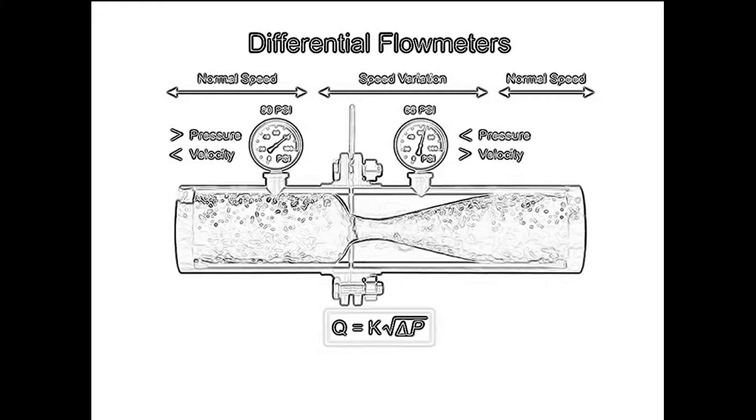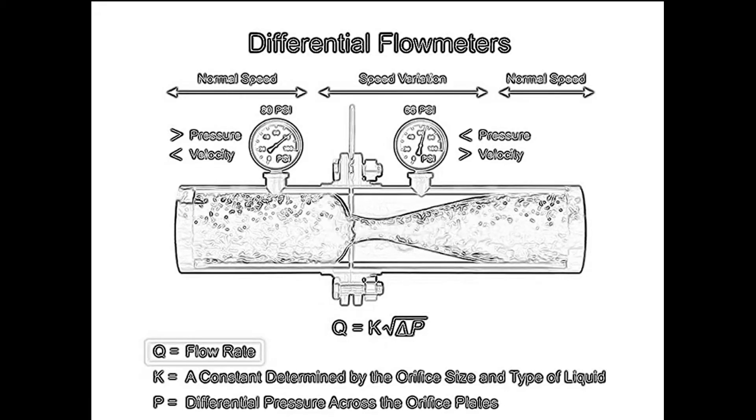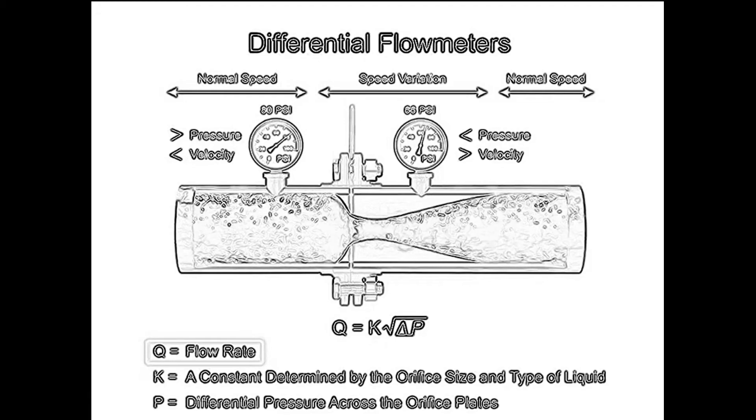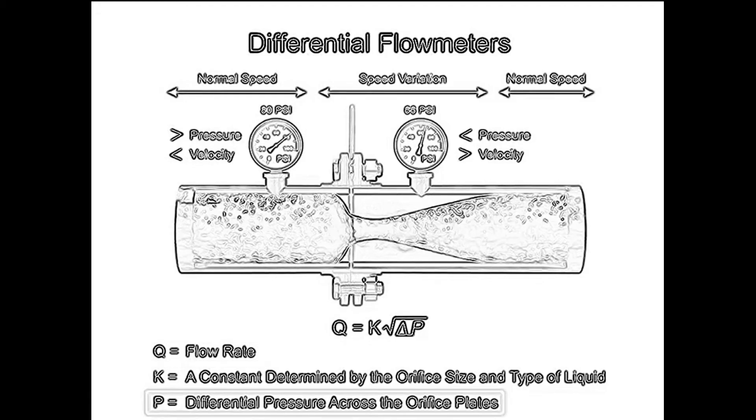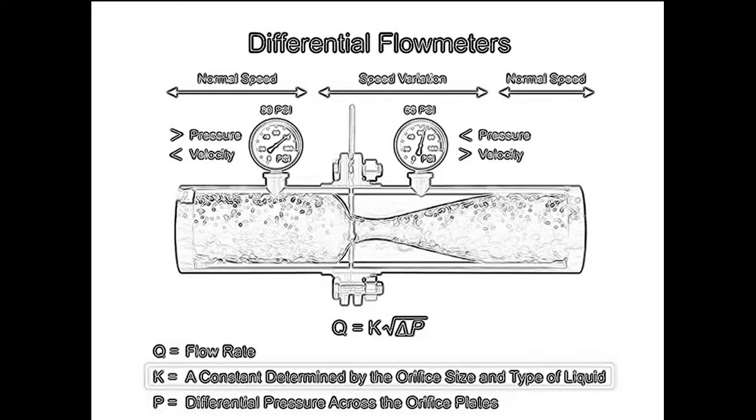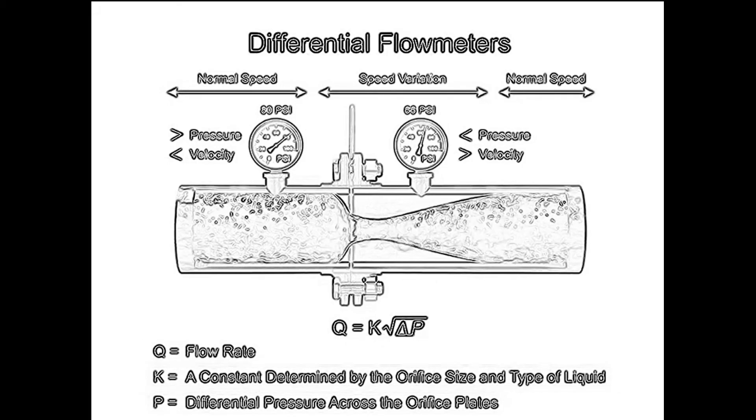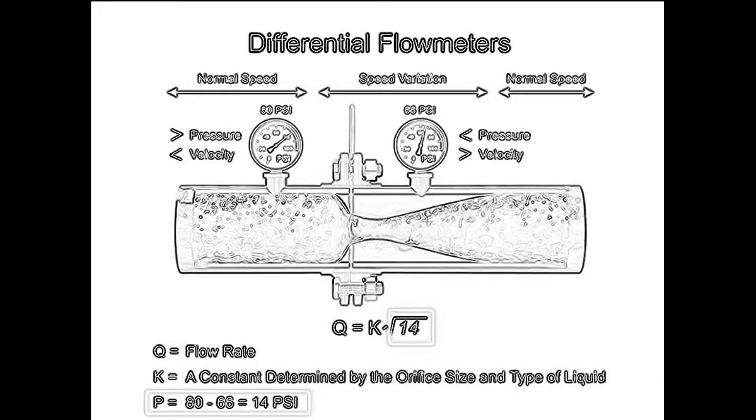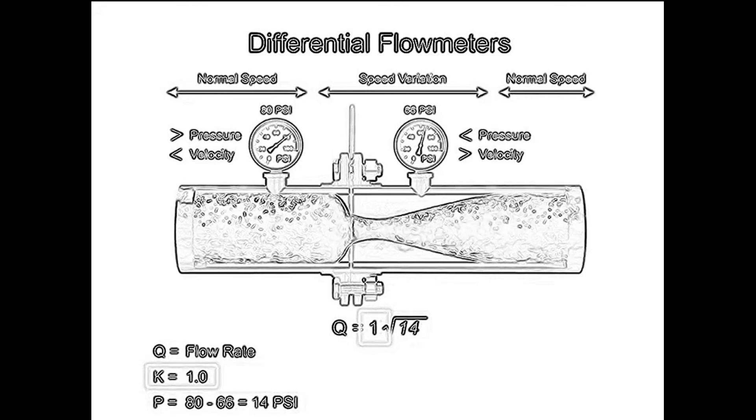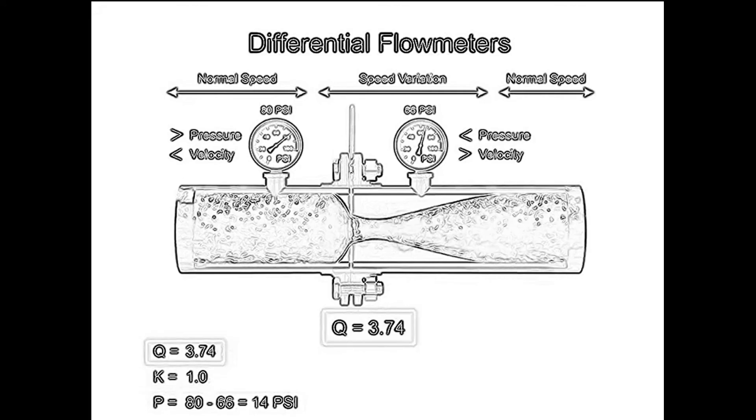The flow rate Q of a fluid through an orifice plate increases in proportion to the square root of the pressure difference on each side multiplied by the K factor. For example, if the differential pressure increases by 14 psi with a K factor of 1, the flow rate is increased by 3.74.